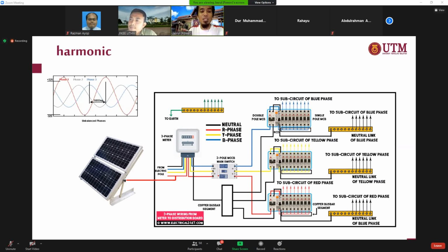So that's why it is recommended that if you are using a three-phase system, you use a three-phase inverter, so that the injected power from the PV can be balanced. There's no problem using single phase since your load is also distributed single phase, but it's recommended to use three-phase so that whatever power is injected will be equally distributed for each phase.